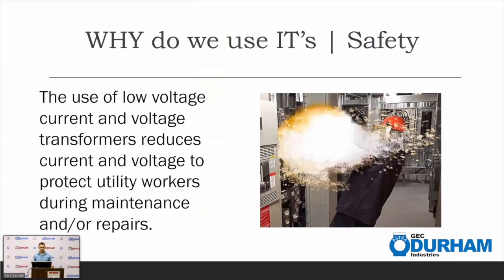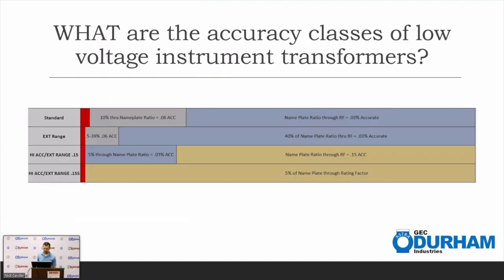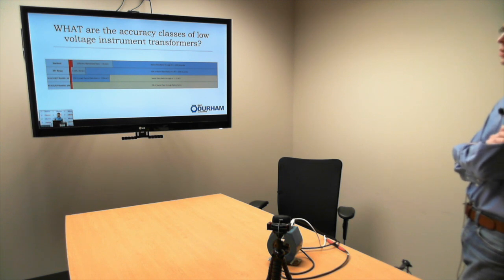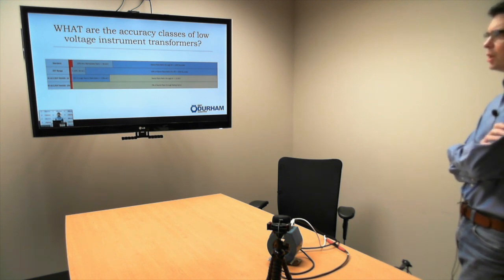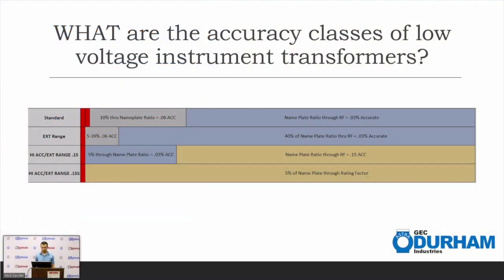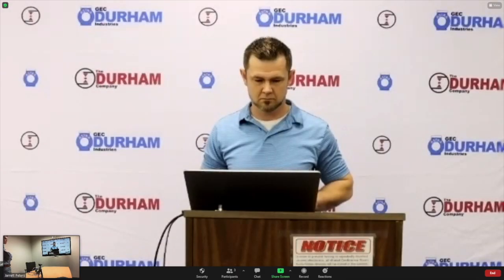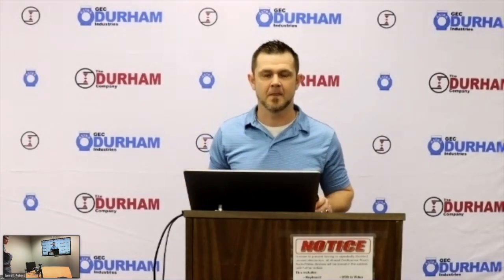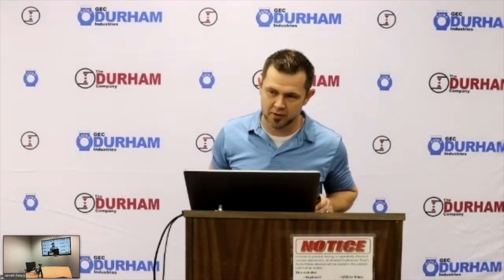Real quick, Nick, go back. Yeah, go ahead. On that previous slide you were talking about, I wanted everyone to see the big difference between the standard and extended range. Notice that on the standard CT, we can go all the way down to 10% of nameplate value and hold the manufacturer's specs, but with extended range, we can go all the way down to 5%. Big deal. Yeah, and I want to make a correction there. That's 4%. The ANSI standard for extended range transformers is actually 4%, so that's a typo on my part. But, excellent. Thank you.